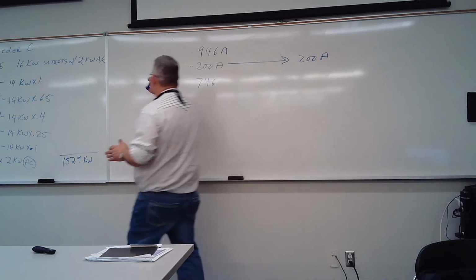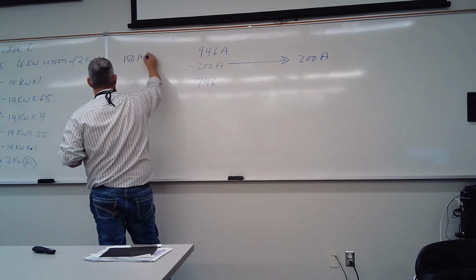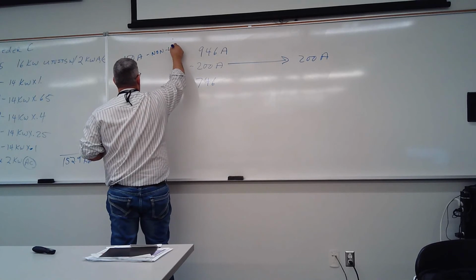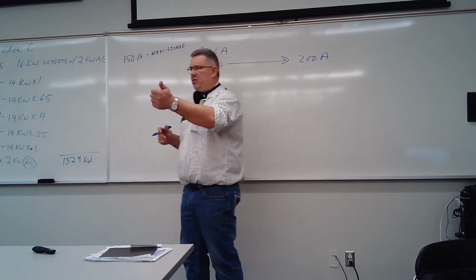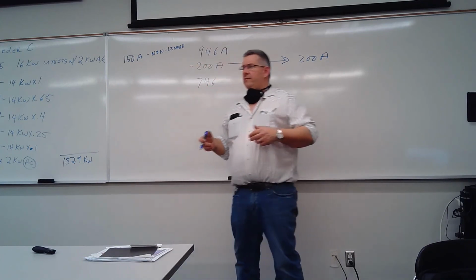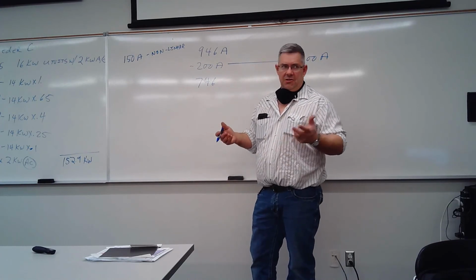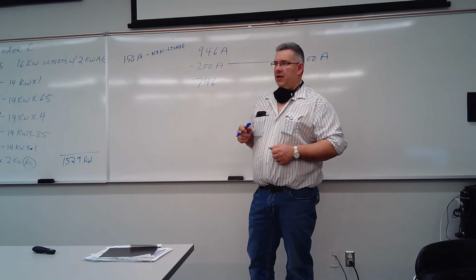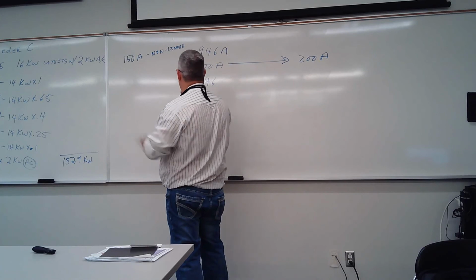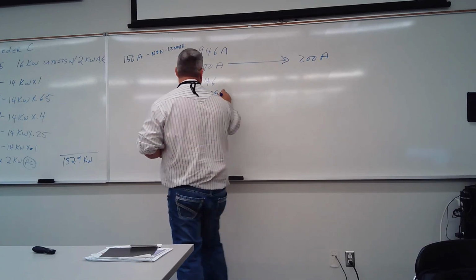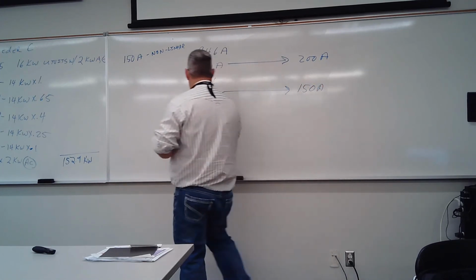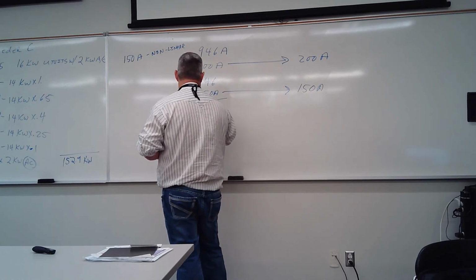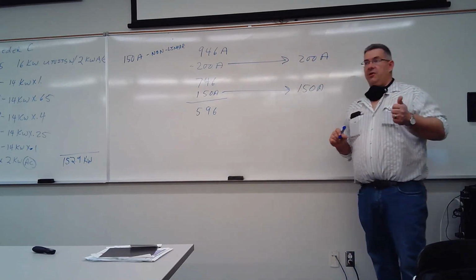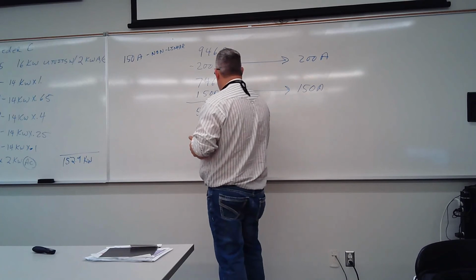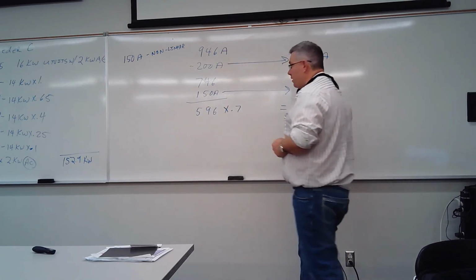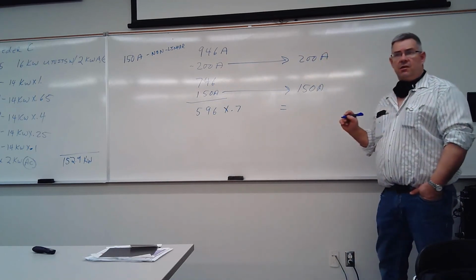So if in that building we determined that 150 amps of the load was nonlinear, so there's a big VFD running the air handling unit, and we've got high intensity discharge lighting outside and all that kind of stuff, that calculates for 150 amps of that service. We can't delete or reduce any of that. So we have to take this out. So that's going to give us 596. Neutrals can be reduced to 70%. So we take 596 times 0.7. 596 times 0.7 equals 417.